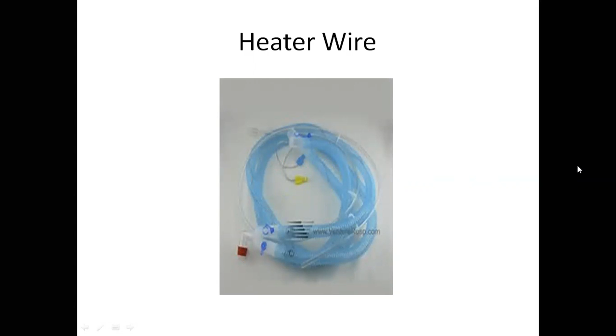And so it's really a nice system. And Hudson and Fisher-Paykel both make them for their devices. They also have temperature probes here and here, so that device knows, okay, there's the temp here, here's the temp here. I'll turn the heater on or off to make sure I maintain that same temperature so we don't get any sort of positive or negative temperature gradient, so that gas stays at 100% humidity when it gets to the patient. Really a nice system. And when you get a chance in your clinicals, if you haven't seen it yet, make sure you hit your preceptor up and see if they'll show you these particular circuits. They both have similar heater wires, obviously different types of hookups to their heaters, but nonetheless, the principle is the same.